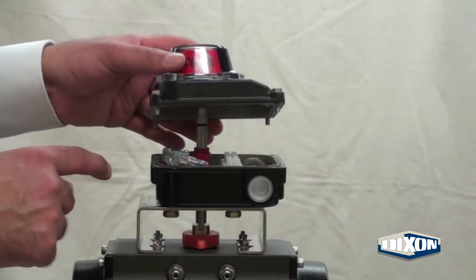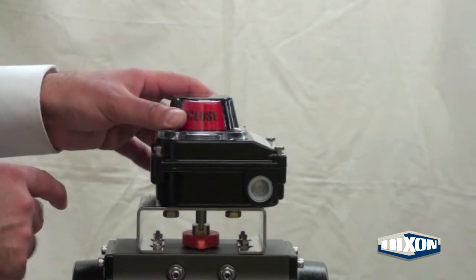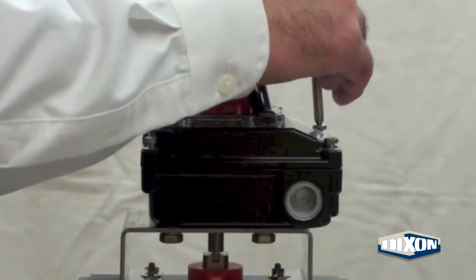Make sure the gasket is completely in the groove of the switch body. Place the cover on carefully so the shaft goes into the square hole in the indicator. Tighten the four bolts on the limit switch cover.